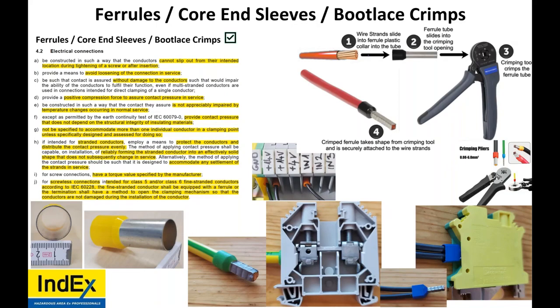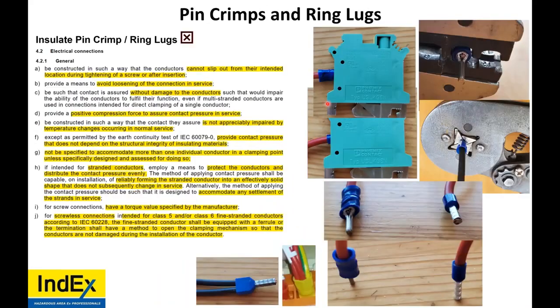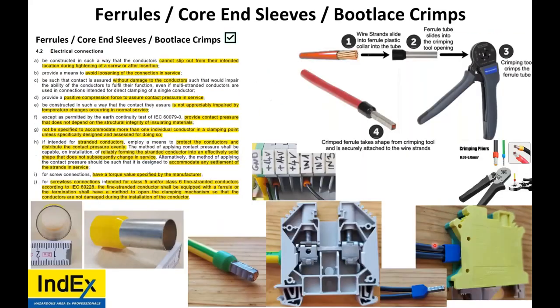Now, can an EX enclosure use a ferrule without the insulated bootlace? Yeah, you can still use a ferrule that doesn't have the insulated collar, but it's highly suggested because you guarantee your creepage and clearance distances. Now, I already showed you the examples, there you go, look at the ferrule, it goes all the way into the terminal, while the insulated pin crimp, you're struggling to get it in and usually it does not get all the way in correctly because it's not designed for EX. It is not designed for reduced creepage and clearance distances. It's designed for commercial and marine applications. Once again, creepage and clearance distances, quality.